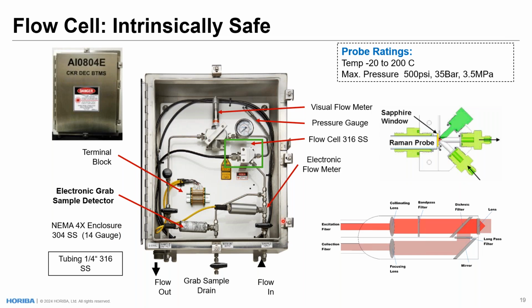Some important components of our flow cell here is this sapphire window that is shown in this little diagram. This image is a drawing of the cut through of this green box here. This sapphire window allows for diagnosing a dirty window cell, and also if the position of the Raman probe isn't perfectly situated up against the flow of your process, etc. The analyzer would flash a warning to you that your model isn't as expected, because the sapphire window will start showing a sapphire peak and really alert the end user that there's an issue with the flow cell. So this is just another diagnostic tool that we use.